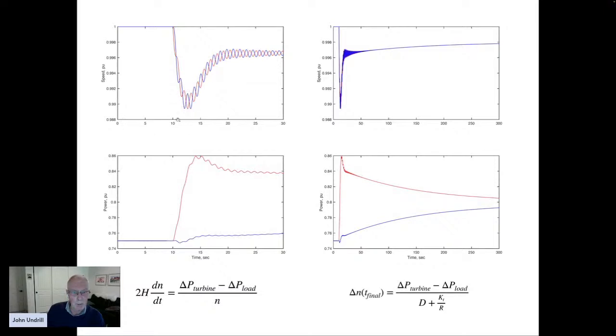I ran the simulation not for 30 seconds. I didn't look at what was going on for 30 seconds. I looked at what was going on for 5 minutes. This nadir here is this nadir here. This peak of steam turbine power here is this peak of steam turbine power here. So if you watch for 30 seconds, you get a false picture of what's going on. You get the impression that one machine's doing all the work and the other machine's taking it easy. In fact, if you wait out the natural characteristic of the system, this equation tells you where you're going here, and this equation tells you how fast you're going to dip in frequency here.